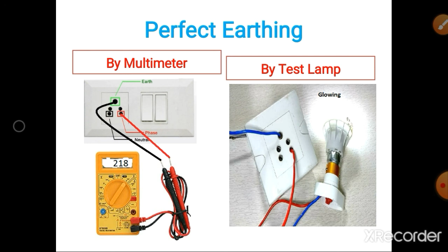If the earthing is not perfect, see this diagram: the red pin of the multimeter is connected to phase and the black pin to earth, but the multimeter shows a reading close to zero, like 005. If you connect the lamp between phase and earth, the lamp will not glow, or it will glow with low brightness. This means the earthing is not done perfectly, and it may create an electrical shock.